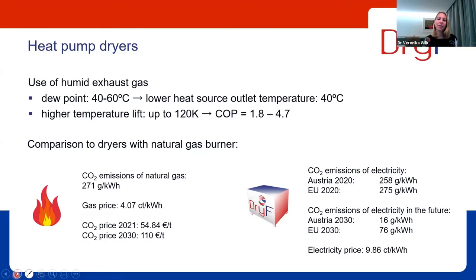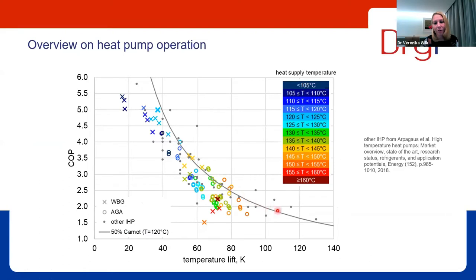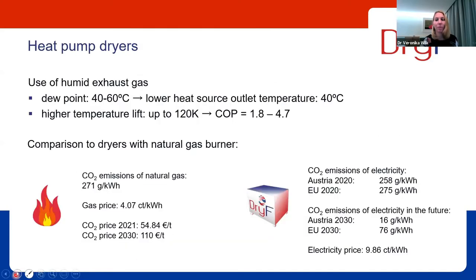And this is just an extrapolation. So if we follow that line, just for orientation, if we go to a higher temperature lift of 120, we end up with a COP of around 1.8. And this will be the lower end of the comparison that I will show you. The COP of 4.7 was one of the higher values that we have measured with the DryFiciency heat pumps at lower temperature lifts.